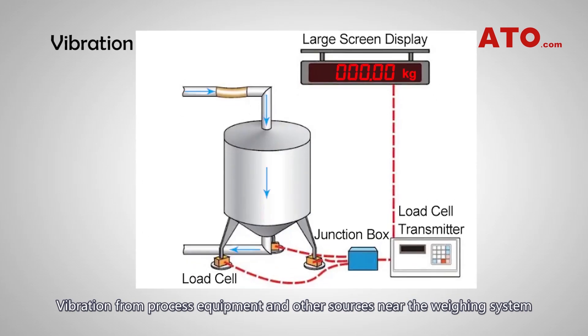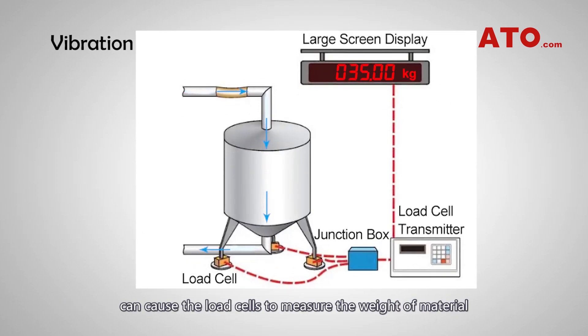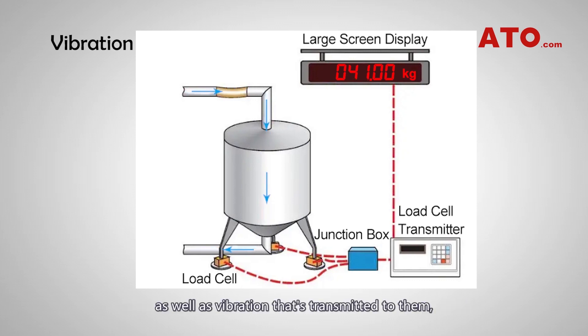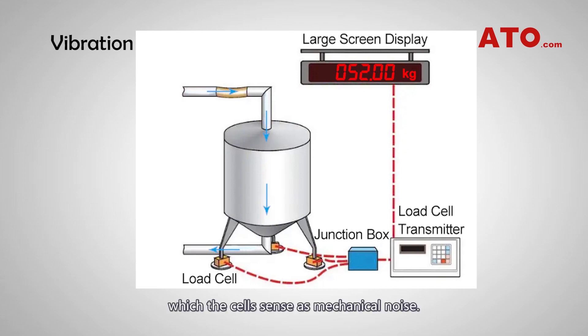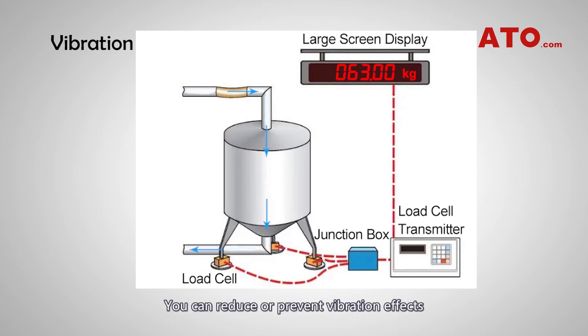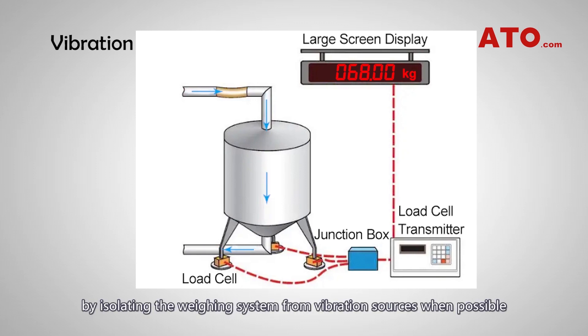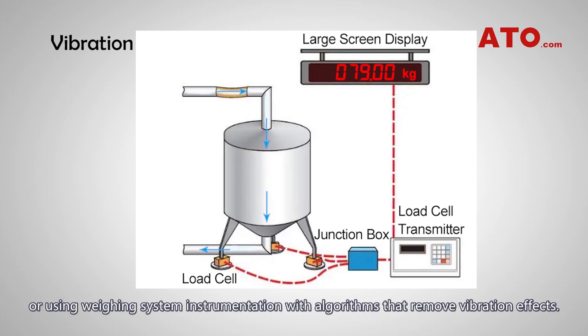Vibration from process equipment and other sources near the weighing system can cause the load cells to measure the weight of material as well as vibration transmitted to them, which the cells sense as mechanical noise. You can reduce or prevent vibration effects by isolating the weighing system from vibration sources when possible, or by using weighing system instrumentation with algorithms that remove vibration effects.